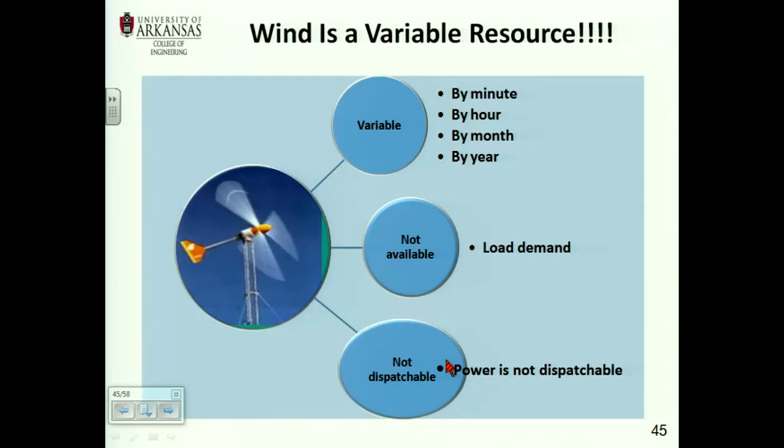Because someone at the control center has to make decisions. If they are forecasting that the wind is going to increase and the load power stays constant, they have to tell some other generator, normally natural gas in this country, could be a coal-fired power plant, but they don't have much margin, to start dropping power.